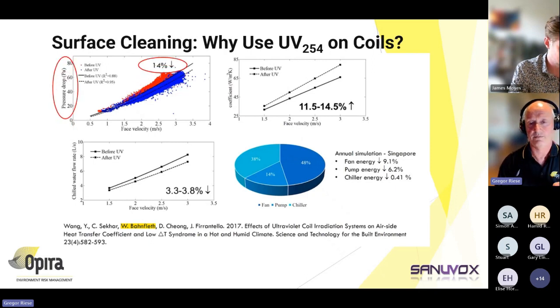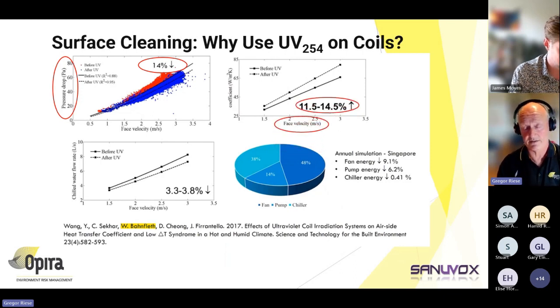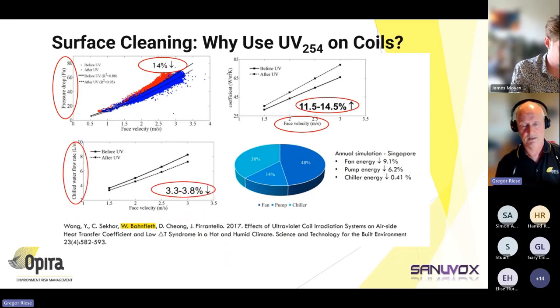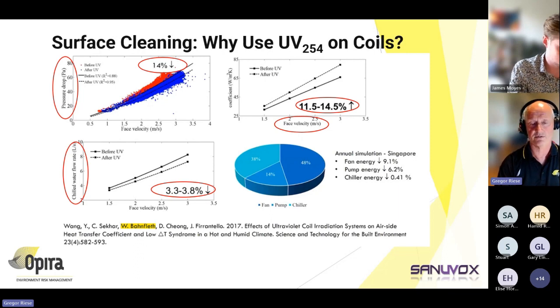Where UV was applied to the coils, there was a significant reduction in pressure resistance across the coil. In this study, face velocities increased and there was a much reduction in chilled water usage - quite typical for these really wet environments where you get biofilm growth on coils. This is one of many studies showing this.